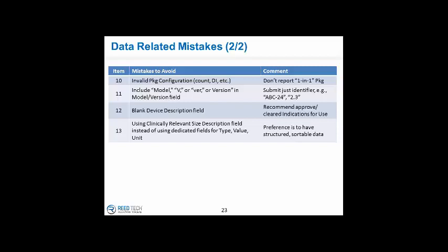And there's no need to report that level to the FDA. It's only when you get to a second level of packaging where you put multiple devices into that package that you report that to the FDA and create a unique device identifier.